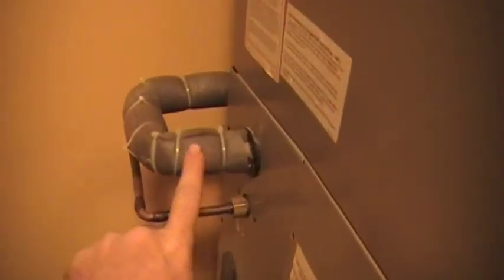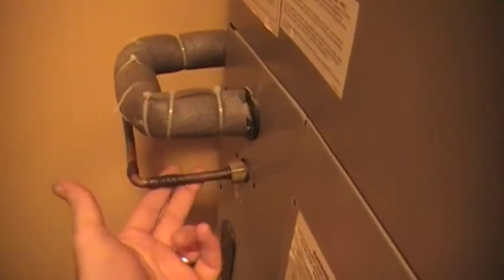Okay, now we're inside. This is going to be the air handler or indoor unit for the condensing unit outside that we've been talking about. So this is going to be the other half of the split unit. And all it is, it's a metal housing. It's going to have an evaporator coil in it. And here's your suction line coming in, and here's your high pressure liquid line where it comes in.